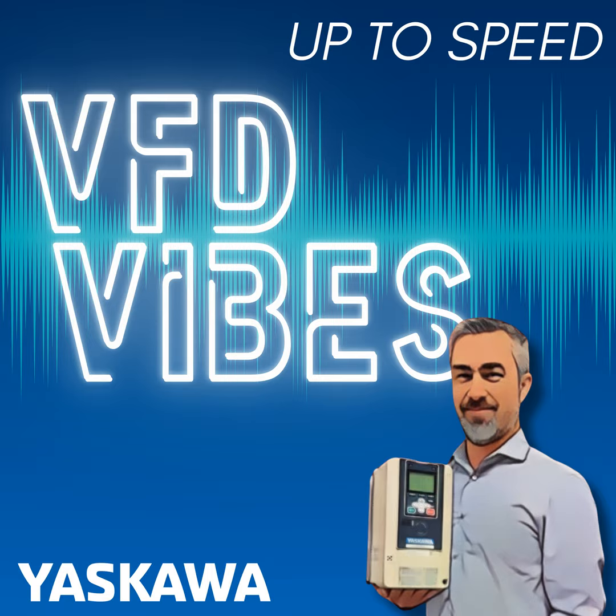What happens if we do all this and our motor's turning the wrong direction? It's always important, after you start up the drive, to check motor rotation. And in my experience, for whatever reason, it always seems like it's running backwards. You always got to make a change. And you can do that two ways with a VFD. You can change it digitally through a parameter, which will digitally swap two of the output legs, or you can swap two of the legs on the output side of the drive.